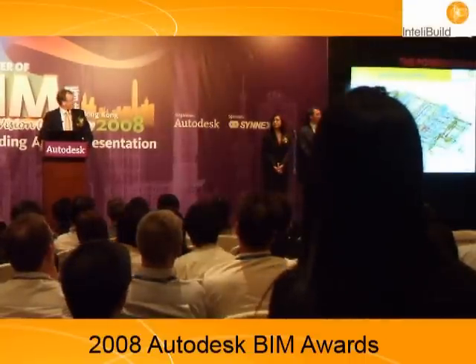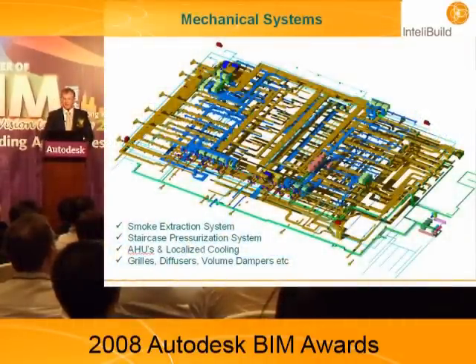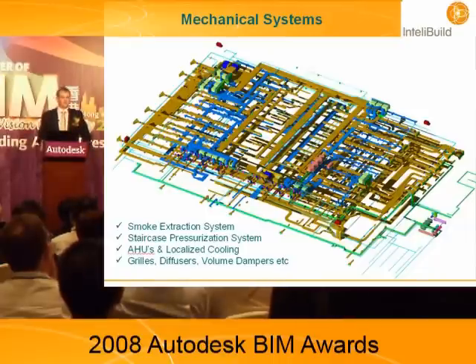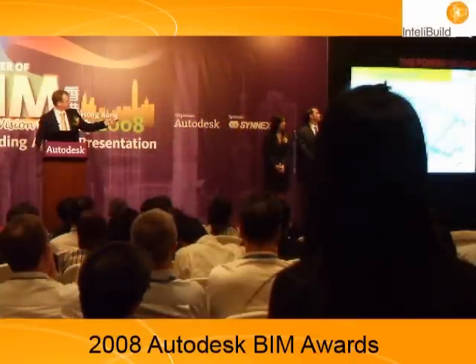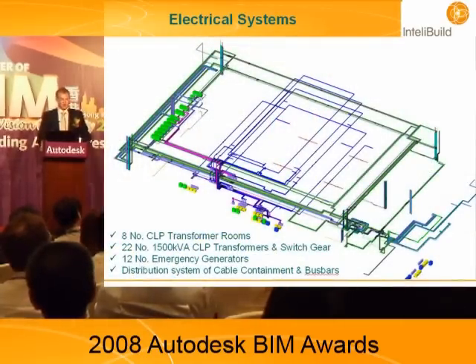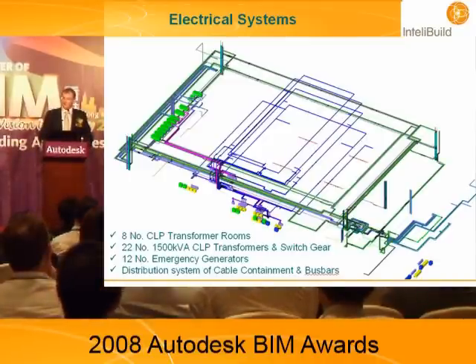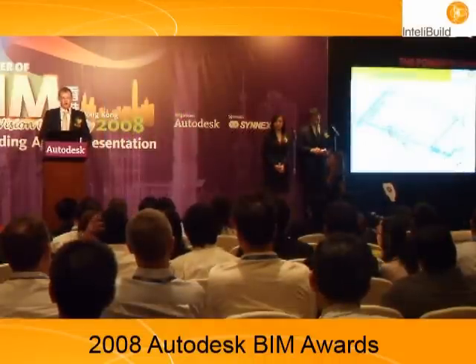This building has very extensive building services. The building is not air conditioned — it is mechanically ventilated for the greater part — but there's a very extensive smoke extract system. We have a dual-purpose ductwork system: in normal operation it ventilates the space; in a fire scenario it becomes an emergency smoke extract system. With thousands of motors moving hundreds of cargo pallets, we need quite a lot of electricity — 22 transformers in the building and 12 backup emergency generators.